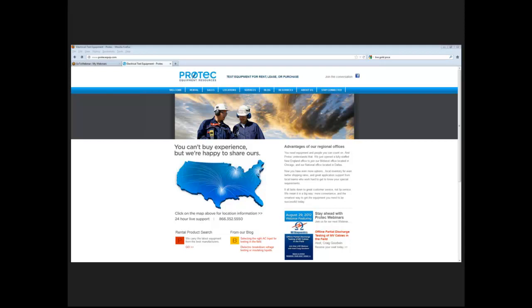Perfect. And does it matter what you calibrate the test at? For example, if you calibrate at 5 nanocoulombs, will that hide partial discharge levels below that? My recommendation is to try to calibrate at the lowest possible value that you can. With some important points being, you need to make sure you get a reflection from the far end of the cable, and you need to make sure that the PD impulse, the calibration pulse, is bigger than your noise band. If you can meet those two criteria, keep the PD calibration pulse as low as you can.